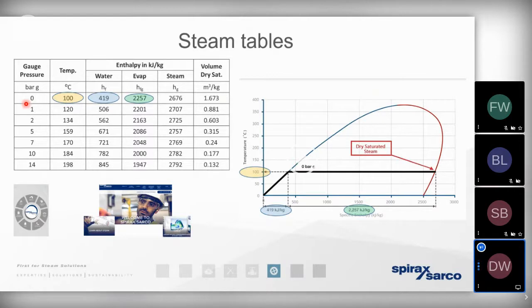And if we move across to the temperature enthalpy curve, this demonstrates the journey that water takes as it changes state from a liquid to produce steam as a gas. So if we take the example of 0 bar gauge, where we know water boils at 100 degrees, you can see that water starts to change state to steam. The evaporation process begins, but only when we've added 419 kilojoules of energy to it. The water then continues to evaporate, and the evaporation process only ends when we've added that full enthalpy of evaporation, latent heat energy, into it.